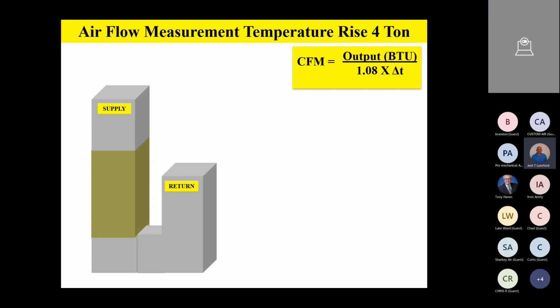I would say probably. Now the downside would be you wouldn't know if you did. You'd know what the CFM is, and you'd be able to extrapolate back as to what the speed tap you're on in the air handler. Obviously, you'd be able to observe that, but you wouldn't know how much static's on the supply and how much static's on the return. So it would be valuable information, but there'd be no way of knowing what my supply static was and my return static. Now you could do something like this. If you know what the CFM is, and you could take the static pressure on the supply, whatever that static pressure was, whatever's left over has to be on the return, right?